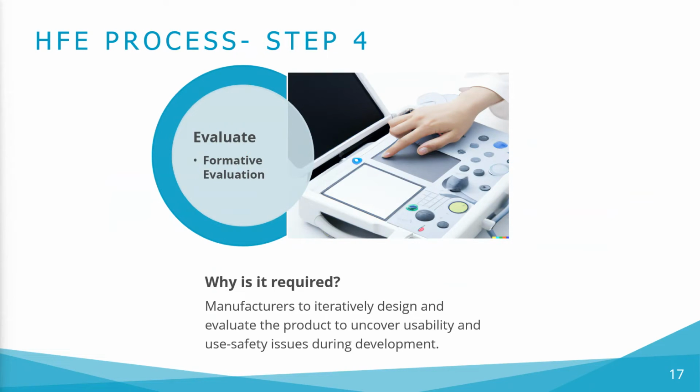HFE process step 4: evaluate. During the evaluate step, the manufacturer should test drive the product. The purpose of conducting these evaluations, typically called formative evaluations because they are performed while the design is still forming, is to identify opportunities to improve the design. Manufacturers are well served to conduct a few formative evaluations to ensure they arrive at a final product that is sufficiently safe, effective, and satisfying to use.